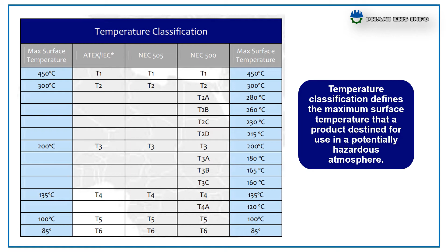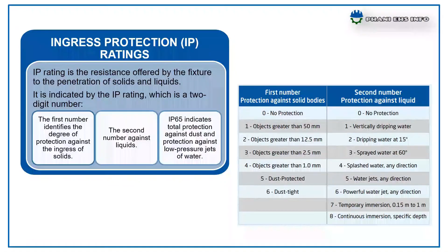Next one, ingress protection, IP ratings. Ingress protection of equipment must be suitable for prevailing conditions at the point of use. IP rating is the resistance offered by the fixture to the penetration of solids or liquids. It is indicated by the IP rating, which is a 2-digit number. The first number identifies the degree of protection against the ingress of solids, the second number against liquids. IP65 indicates total protection against dust and protection against low pressure jets of water.